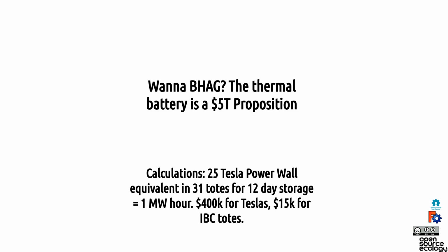How much would that cost? Do the calculations: water going up 30 degrees Celsius, from about 20 to 50, or 10 to 40, 20 to 50 or so. The thermal storage capacity of water is huge. So 31 of those tanks get you 1 megawatt hour—we're not talking kilowatts, we're talking 1 megawatt hour of thermal energy. This is nuts.